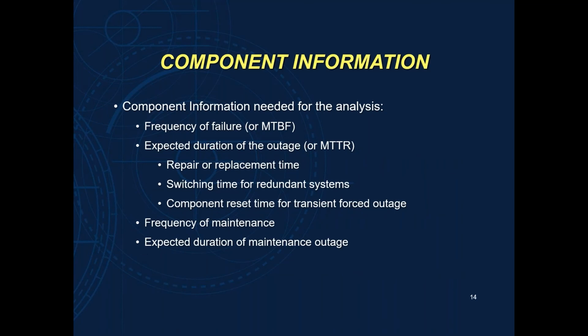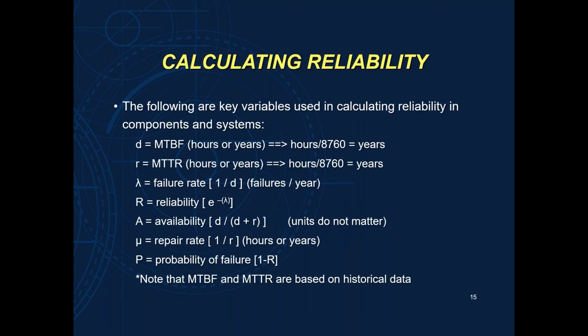The values that we discussed before, the mean time between failure or the mean time to repair, this is all information that you should be able to get from your maintenance records, okay? If you cannot, these are also provided in the Gold Book. So if we're going to calculate it, some of these values that you see are the words we've talked about, and I have a little example here that shows you how you calculate these values as you assemble your data. Keep in mind that each one of these values is not necessarily just for one component. It might be for your entire system as a whole.